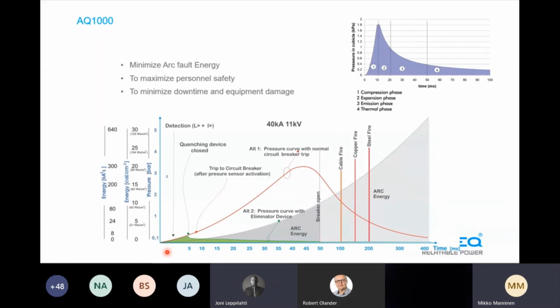Mikko. Yes. Mikko wanted to point out that you should not leave the commissioning input activated more than 24 hours, because it will put the quenching device into disabled mode. Very good point. Yes, this is important. There are some details: during the commissioning the switch has to be on, but the commissioning switch should not stay on over 24 hours. Thank you.